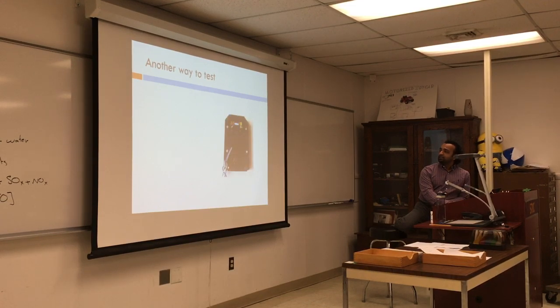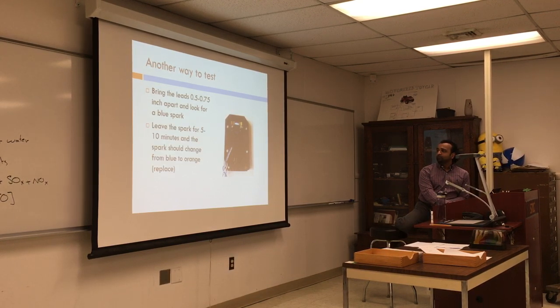Again, another way to test, and this is the least reliable way, is just checking the color. It's very subjective to what you see, the time, the gap. They say bring the gaps together and look for the spark. Leave it for 5 to 10 minutes and it should not change color. And again, a new transformer will always give you a better spark. But I don't like this method because it's not very reliable. The better way is to put a meter in there and check the amperage drop.